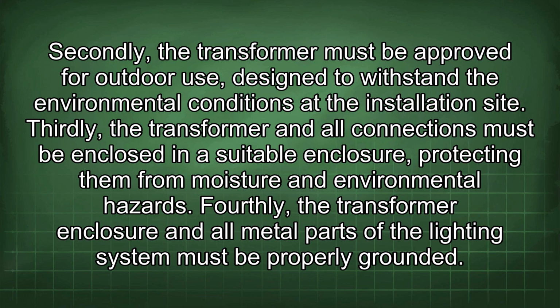Secondly, the transformer must be approved for outdoor use, designed to withstand the environmental conditions at the installation site. Thirdly, the transformer and all connections must be enclosed in a suitable enclosure, protecting them from moisture and environmental hazards. Fourthly, the transformer enclosure and all metal parts of the lighting system must be properly grounded.